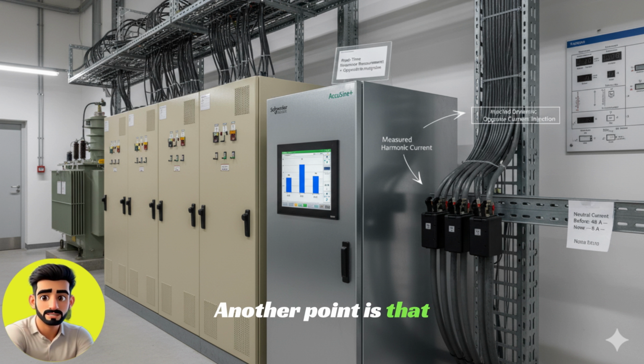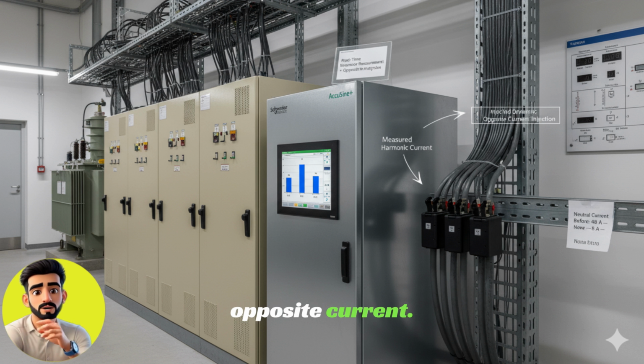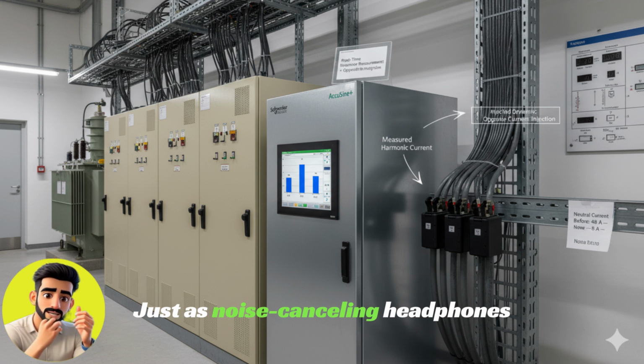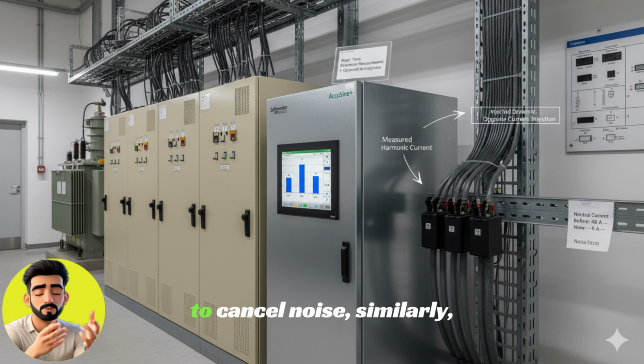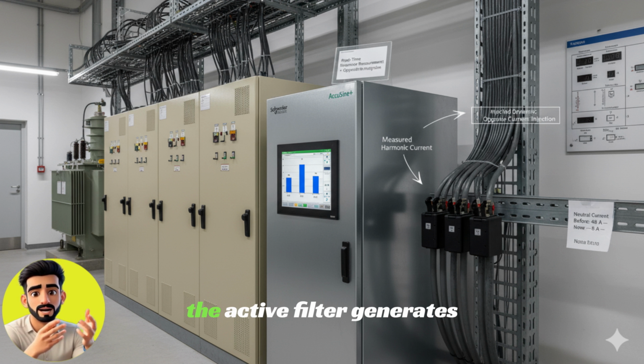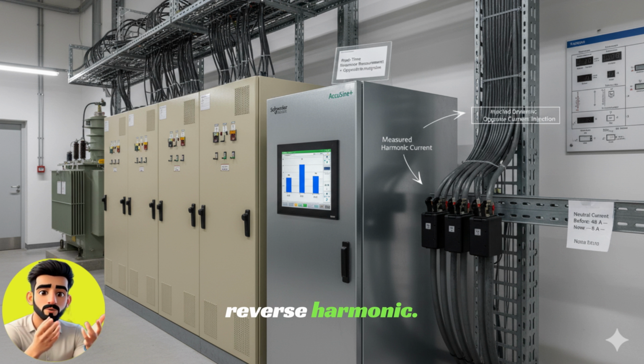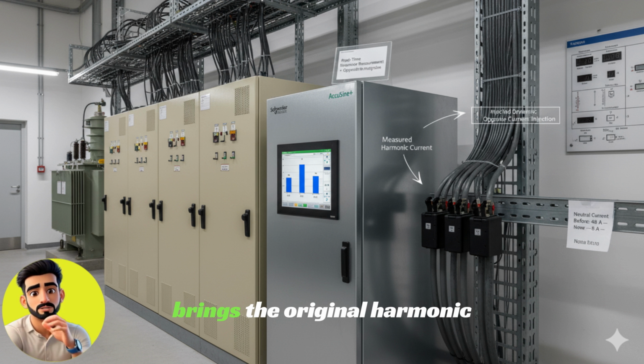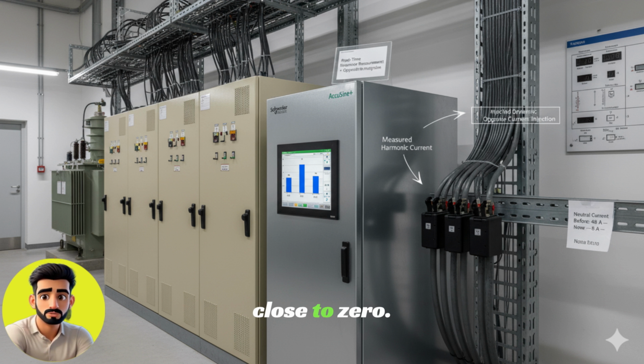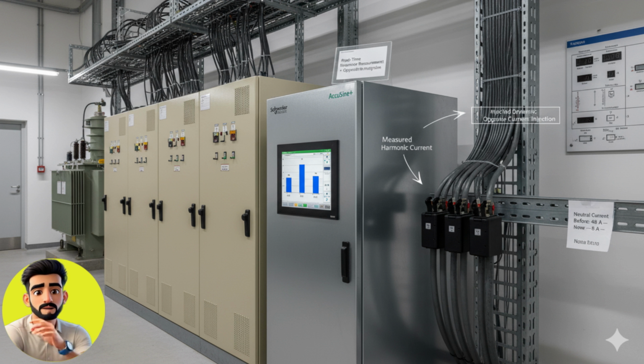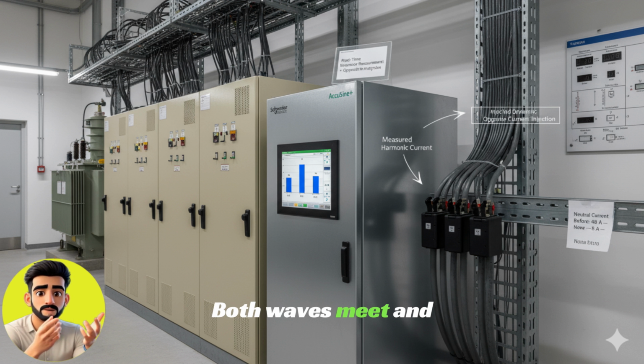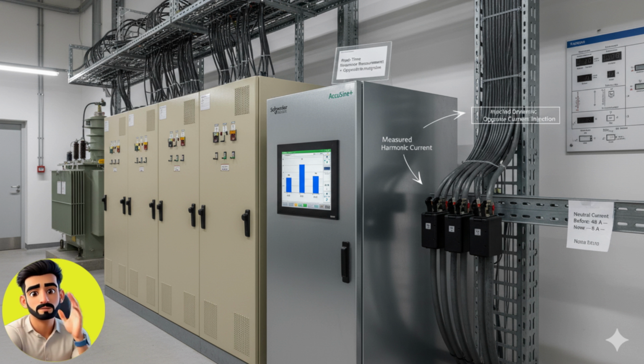Another point is that the active filter injects opposite current. Just as noise-cancelling headphones generate reverse sound waves to cancel noise, similarly, the active filter generates reverse harmonic current and injects it, bringing the original harmonic close to zero. Understand this in simple language. If an unwanted wave is rising in the system, the active filter generates a wave downward. Both waves meet and the harmonic cancels out.